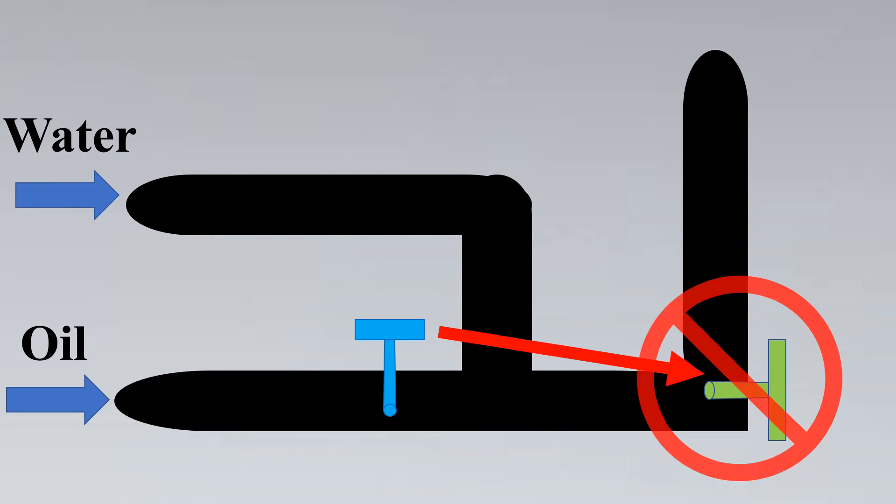Is the process interested to measure the temperature of water and oil together or just that of oil? In this case, this would not be a correct installation. Why? Because maybe the process has certain other demands that need to be taken into consideration. We need to look for such cases.